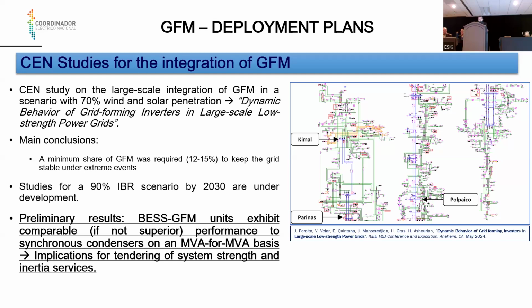The main conclusion of this study was that a minimum share of grid forming was required to keep the grid stable under extreme events. In this case it was 15%, but this is a preliminary figure. Right now we are performing studies for a 90% IBR scenario by 2030, because one of Chile's objectives is to achieve a full phase out of the coal power plants.